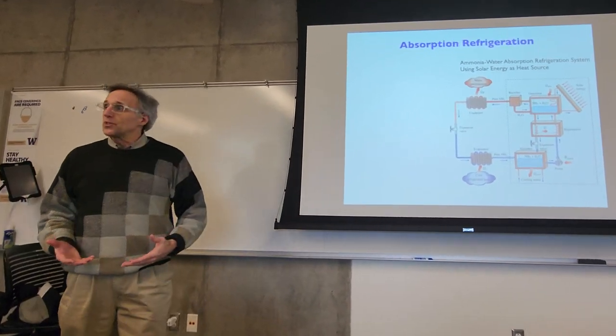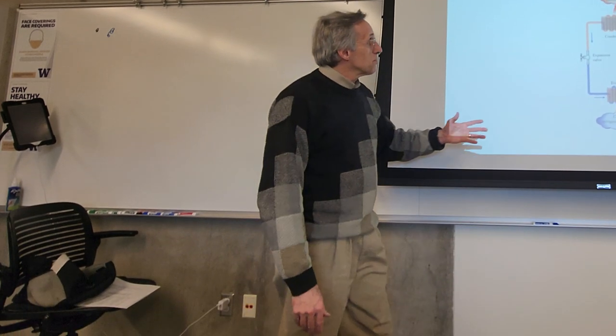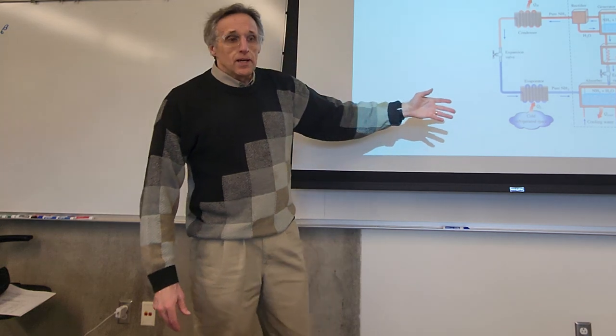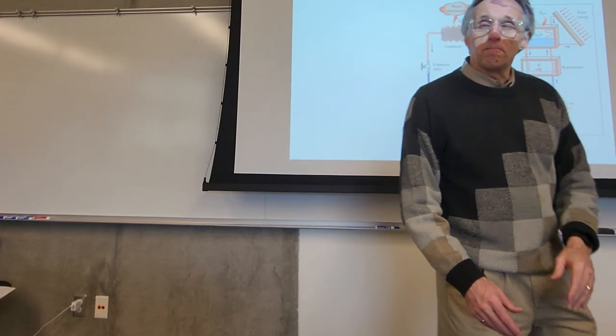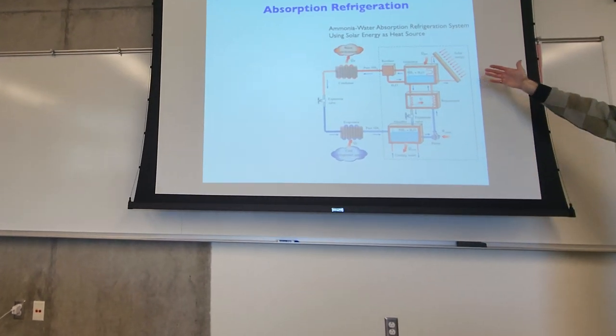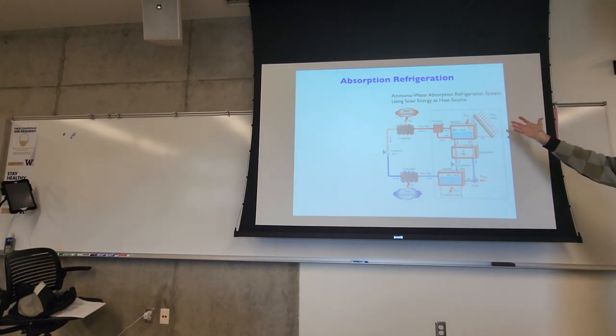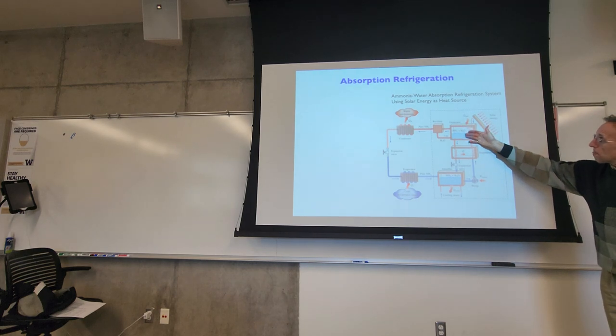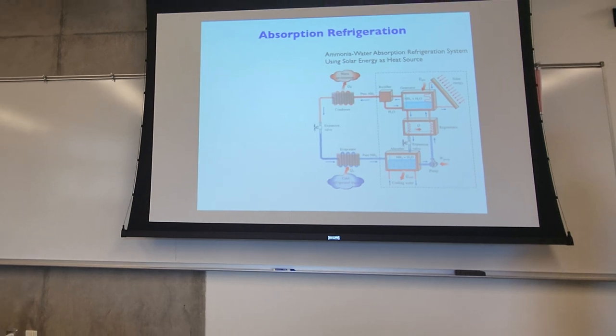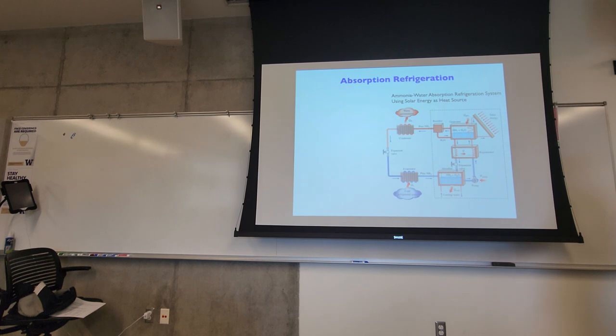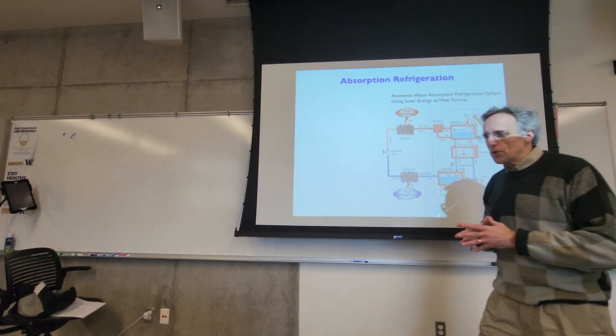But absorption is significant. This is when you've got a really big refrigeration need, or you're air conditioning a really large building or a campus. Absorption cycles, or an absorption system, is the way to go. And UW Seattle has one of these. You'll often see these co-located with the power plant, the building power plant. The reason is that to run an absorption cycle, you need a source of heat. In this case, we're showing solar energy, and solar thermal is a good source, because you need heat to run the process. With a power plant, you can take advantage of the steam, especially if you have extra steam that might get wasted or not used. You can use that steam as a source of heat in the absorption cycle. You also see these in big hospitals that might have large cooling needs.